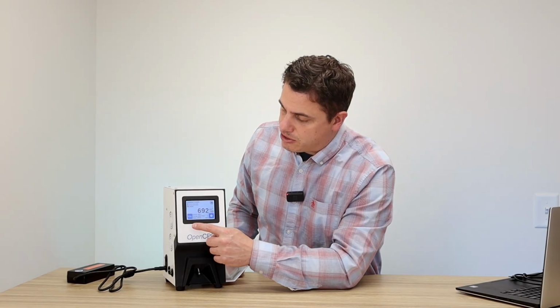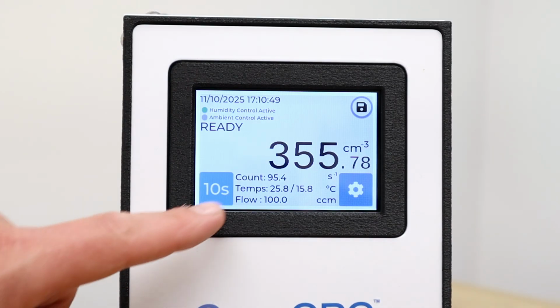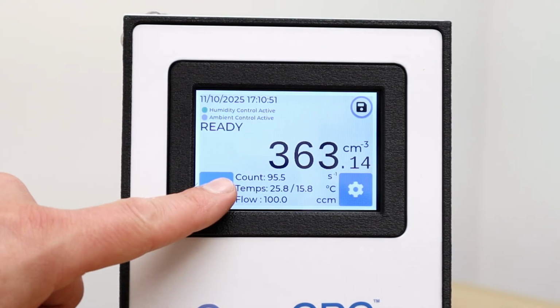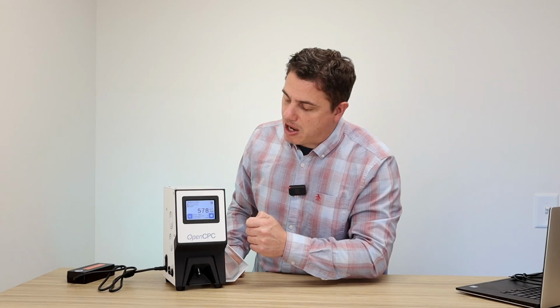Now that we're in ready mode, we can begin logging data. Probably the easiest way is to use the internal logging. To do that, you'll first need to configure your time averaging window by pressing the button in the bottom left to adjust it to different time settings. In this case, we'll adjust it to 1 second time averaging.